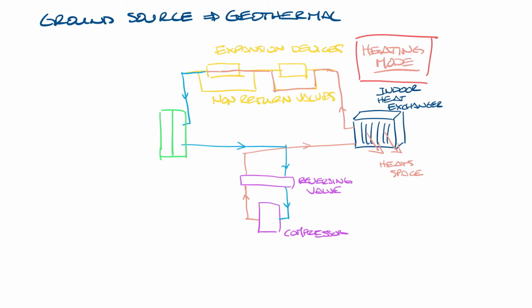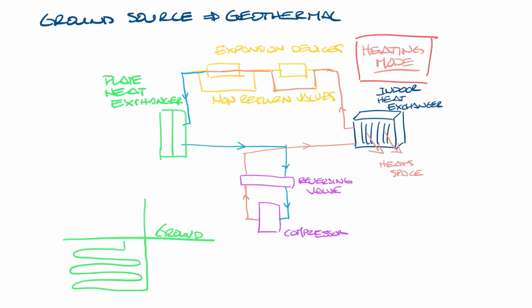You'll have a plate heat exchanger here. One side is connected to the refrigeration loop and one side is connected to the water loop that is buried in the ground. So this is ground level. Below ground level, you would have a water loop or a water plus antifreeze loop that would flow through this side of the plate exchanger. And then the other side is the refrigerant, so your heat exchange is happening between these two sides of the plate exchanger. The loop can be buried either vertically or horizontally. It circulates the fluid that absorbs the heat from or relinquishes heat to the surrounding ground, depending on whether the ambient air is colder or warmer than the ground. And then that is transferred to the refrigerant.